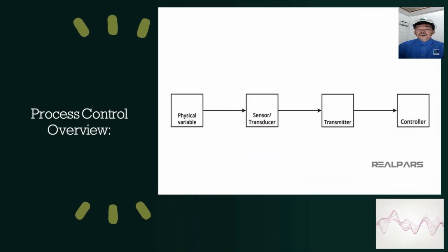This is the process overview of instrumentation. The sensor or transducer is directly in contact with the process variables. Then the output of the sensor becomes the input for the transmitter. For the transmitter, an electronic module processes the input from the sensor or transducer and converts it to an instrumentation signal, normally in the form of analog 4 to 20 milliampere. Then the controller takes the necessary action as required by the process setting. This is also called a block diagram of the instrumentation process.